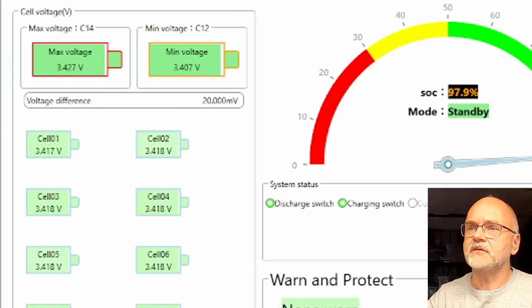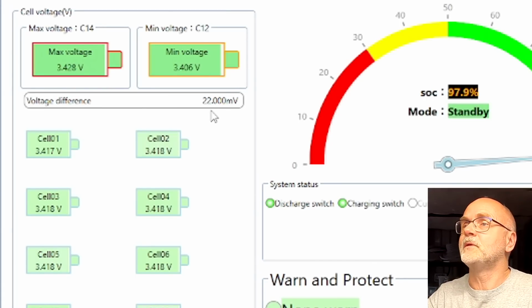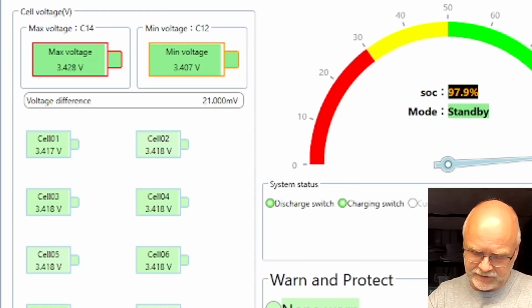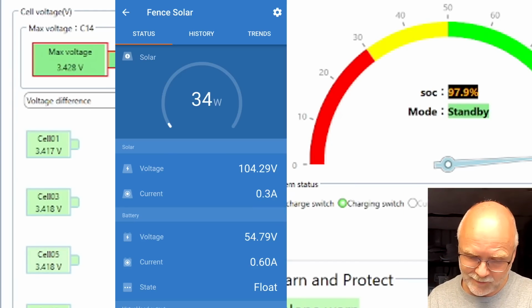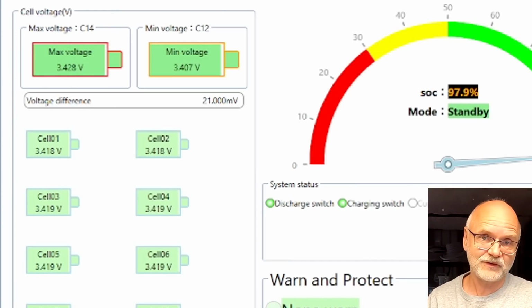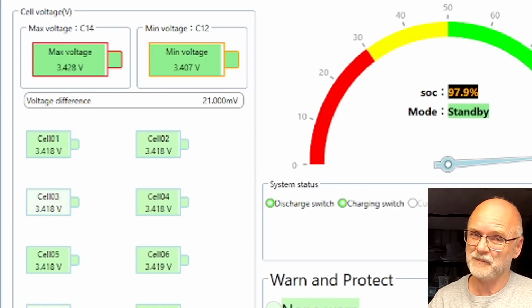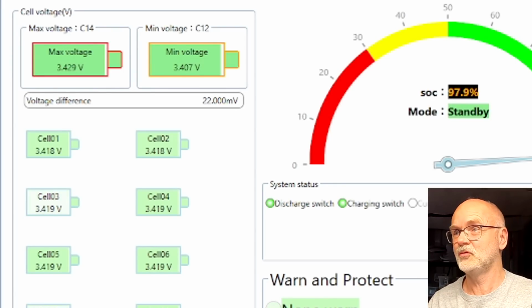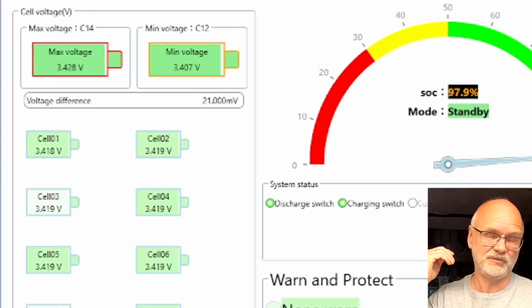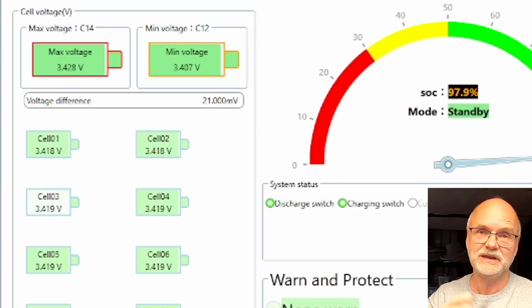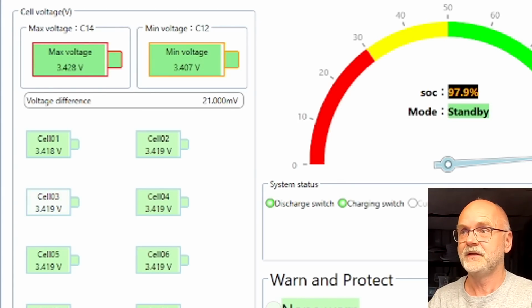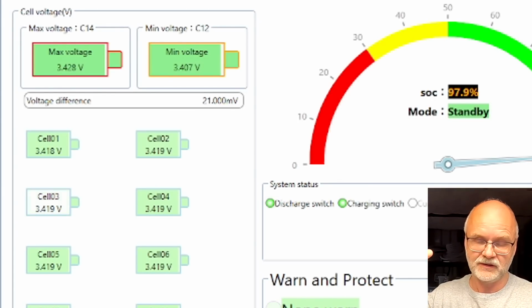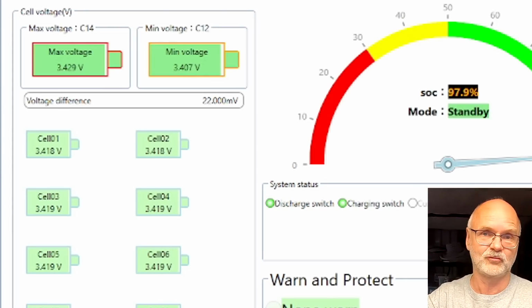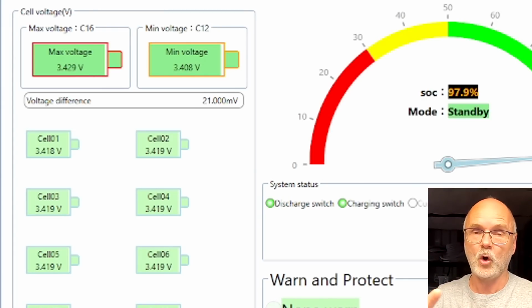Voltage difference is 20 millivolt, 22 millivolt, and we are charging with half an amp only at the moment. The 55.2 volts is probably the maximum you want to charge the battery to, and this gives you already 99.8% state of charge if you leave it there for an hour to absorb.